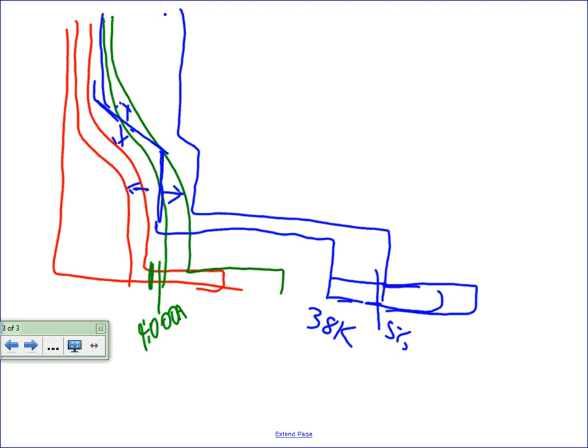Does that make sense? So this is what we get to deal with on hospital jobs every day of the week. Before we even bid the job, we have to do some type of a quick study to make sure we pick the right breakers that are going to coordinate, well, at least what we think is going to coordinate. But we won't know for sure until probably towards the end of the job, when we actually do a full-blown short circuit study, so we know what the fault currents are at each of these buses. And then at that point, we can do a full coordination study to pick the right breakers.